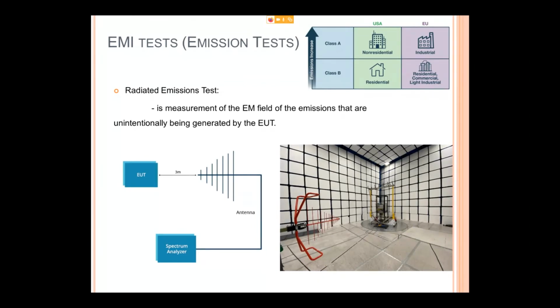So how is the emission test performed? This is also performed at two levels: radiated emission and conducted emission. The radiated emission is measured in the anechoic chamber, measuring the electromagnetic field. That is nothing but the emissions coming out of your EUT. So that emission will be recorded in the spectrum chart, and that will be imported into your device document.